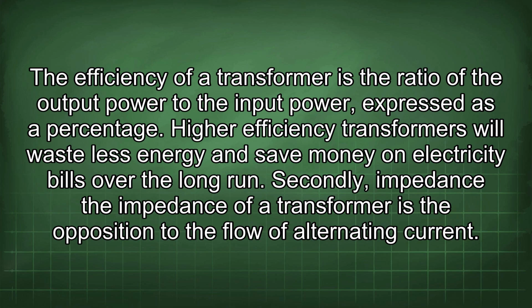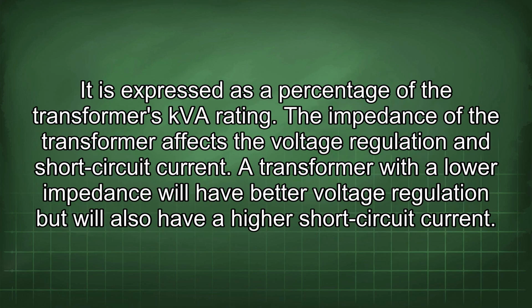Secondly, impedance. The impedance of a transformer is the opposition to the flow of alternating current. It is expressed as a percentage of the transformer's kVA rating. The impedance of the transformer affects the voltage regulation and short-circuit current. A transformer with a lower impedance will have better voltage regulation but will also have a higher short-circuit current.